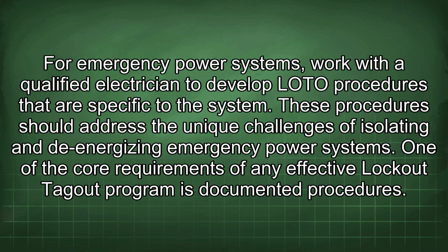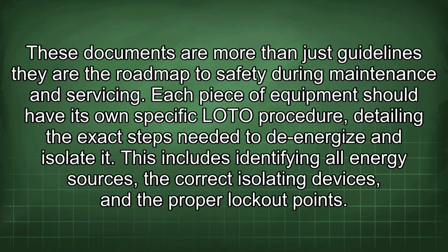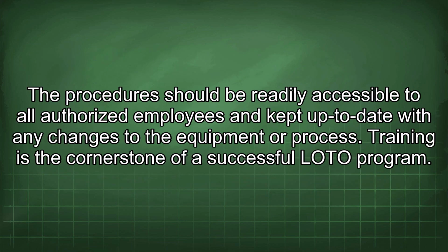One core requirement of any effective Lockout Tagout program is documented procedures—more than guidelines, they are the roadmap to safety during maintenance and servicing. Each piece of equipment should have its own specific LOTO procedure detailing the steps to de-energize and isolate it, including all energy sources, correct isolating devices, and proper lockout points. Procedures should be readily accessible and kept up to date.